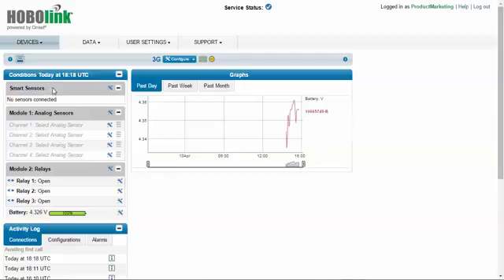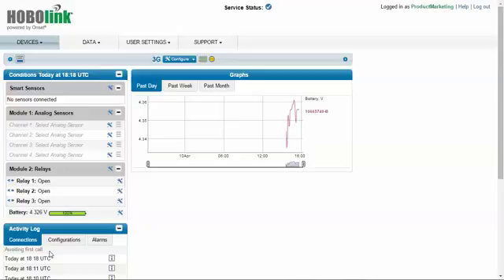We can see we have no sensors connected currently and it is awaiting its first call. When you register a new device, you have to initiate the first call from the RX 3000 station. So what we want to do now is connect our smart sensors and click on start, the start button on the front of the LCD on the RX 3000 to get the device to connect to HoboLink.